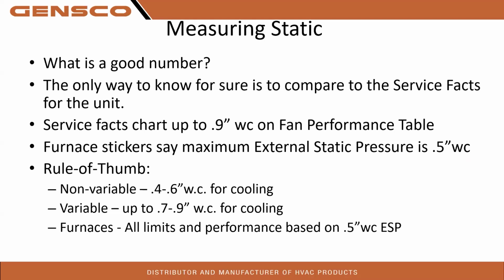0.9 is getting scary, because if it's 0.9 on a brand new system with a brand new air filter, what's it going to be after that air filter gets used for a little bit? So rule of thumb, non-variable speed, it'll be 0.4 to 0.6 inches of water column for cooling. Variable speed, we see 0.7 to 0.9 for cooling furnaces. All limits based on that. ESP is external static pressure. So that's return static plus the supply static is your external static pressure total.